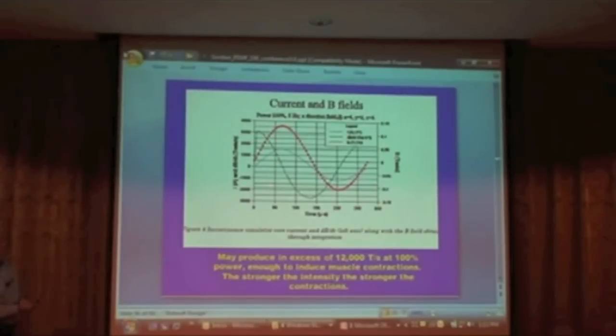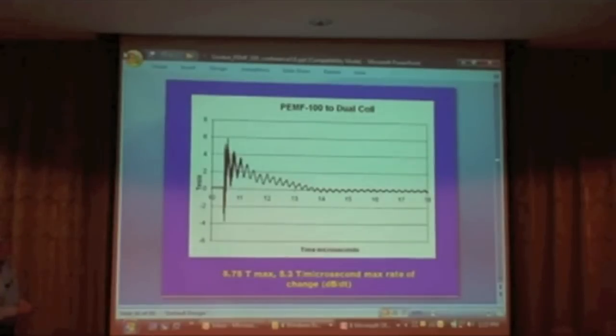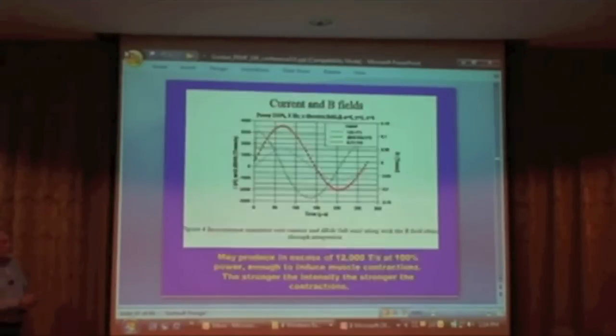Again, this is just another mapping of the current and B fields for the accompanying stimulator. And they've mapped all these, put them simultaneously into one curve. Too complicated, I won't spend time with it. This is the PEMF 100. Jim, this is new. This is in time in microseconds, not milliseconds. Microseconds. You've got 6 Tesla, 5.5 to 6 Tesla, 5.75 Tesla max, 5.3 Tesla per microsecond. Right?